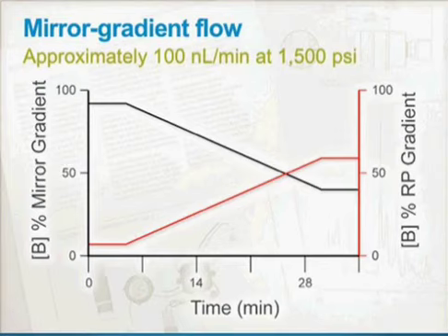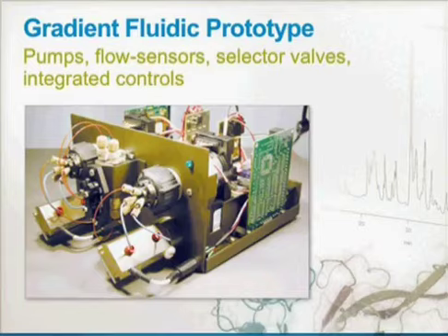So what we had to evaluate was somewhere between 0 and 5 microliters per minute, preferably 100 nanoliters to a microliter per minute flow rates, up to 1,500 or 2,000 pounds per square inch, I think, was about where it ran. How well these two pieces of equipment were going to interact as we performed a separation with one gradient and then counteracted the effects with the chemistry of that on the protein digestion. So what we had was, in the end, I think, Dave, very, very good precision that allowed it to happen, probably within 0.5% precision run-to-run.